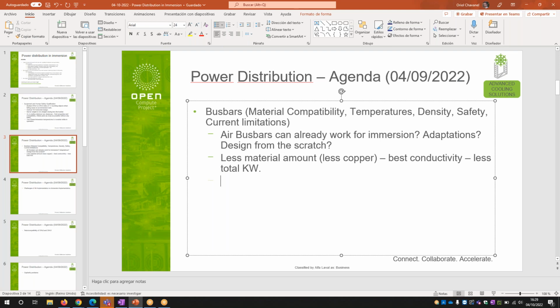Do you think that the adaptation of air bus bars for immersion isn't that different? That's hard to say - I actually think they're pretty substantially different, but I don't know what that evolves to, or what it looks like inside the rack. If you were to optimize the bus bar system for an immersion environment, you might end up with a very different design.